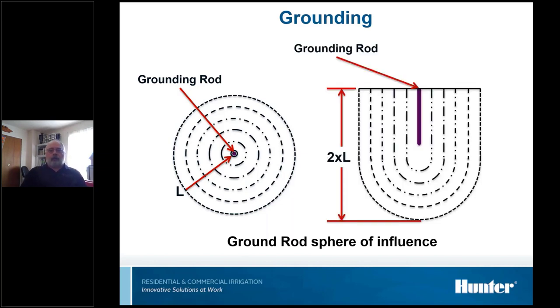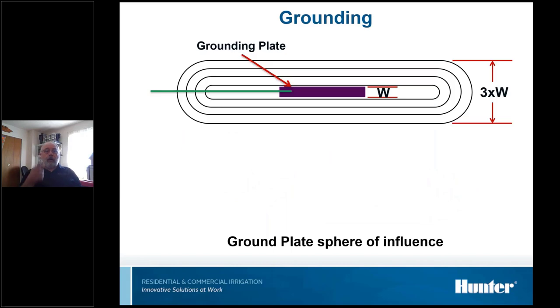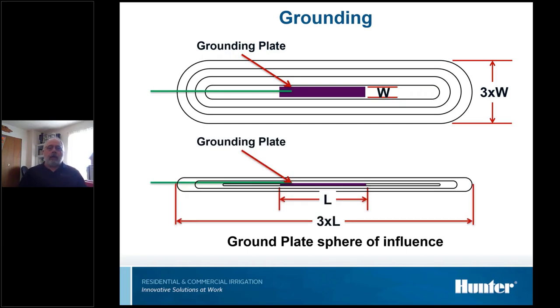And it looks like this from the side. It's twice the length of the rod across, and twice the length of the rod deep. The depth really doesn't matter. There's nothing down there that we care about anyway. There are no pipes or wires down there. It's the area around it that's of concern. So with the grounding plates, the sphere looks quite a bit different. It's still the same thing. It's twice the length, twice the width. The shape of it is quite a bit different, and you need to be aware of that when you're installing them. Just the nature of the plate, it doesn't go very deep. The sphere doesn't go down deep like it does with the rod. Again, it doesn't really matter. We don't care what's down there anyway.